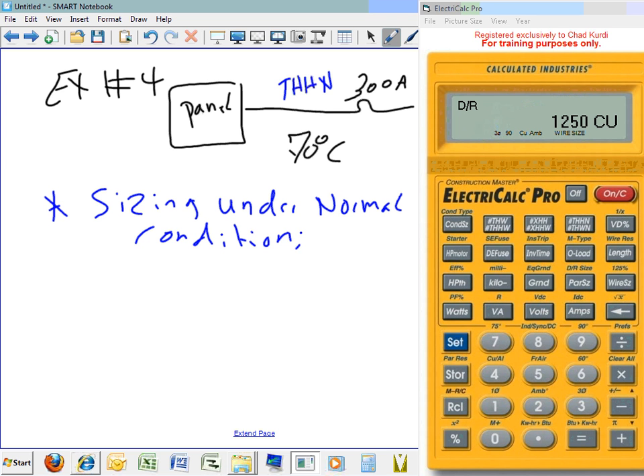How do you size under normal condition? The panel size, the overcurrent device is given to you. You're going to go directly and find a conductor. Under which column and why? 75. Why 75? We have 100 or more than 100, right? So piece of cake.